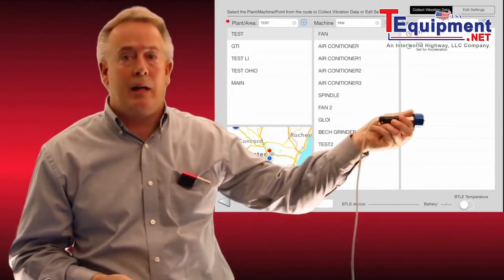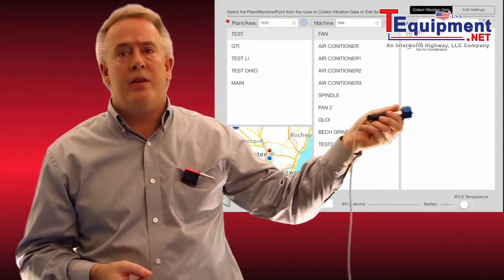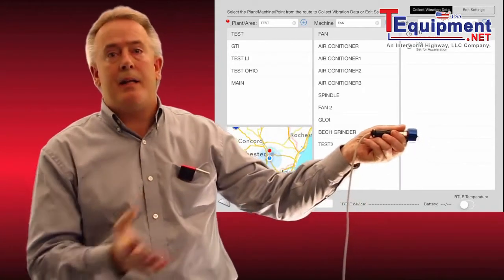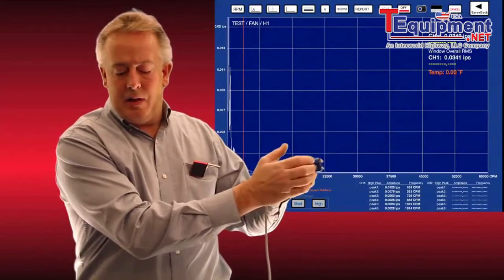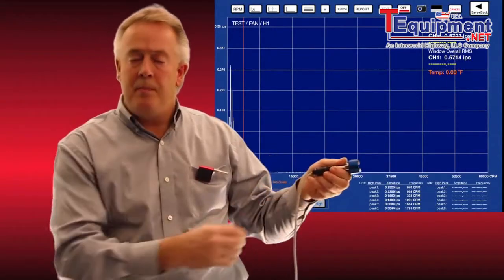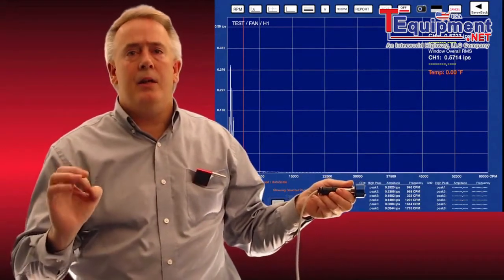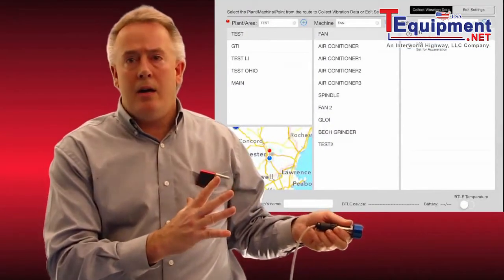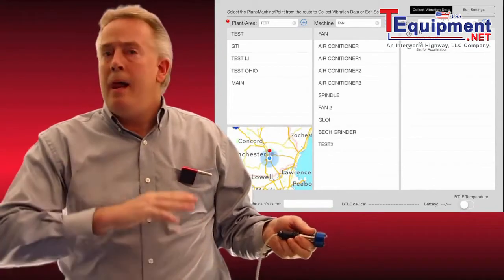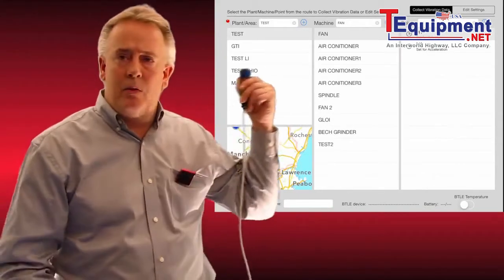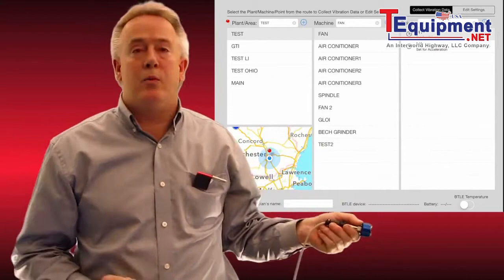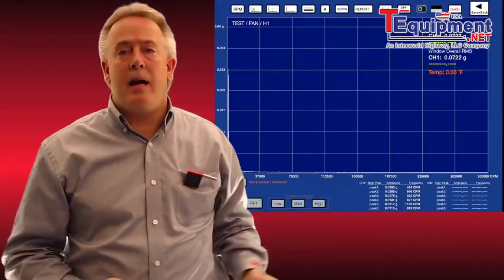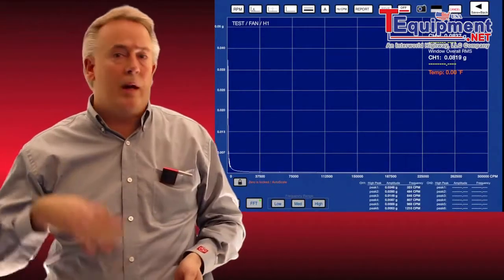All the technician has to do is put the sensor in the horizontal one position — there's a photo to see where the previous technician placed it. As soon as you highlight that measurement point, the spectrum comes up. The technician just taps a bit to get a spectrum, hits the save and back button, and it goes back to the hierarchy screen. He's done with that measurement point, moves to H1 acceleration, takes his measurement, hits save and back again — and he's done.